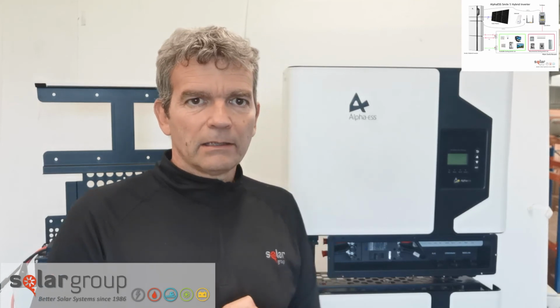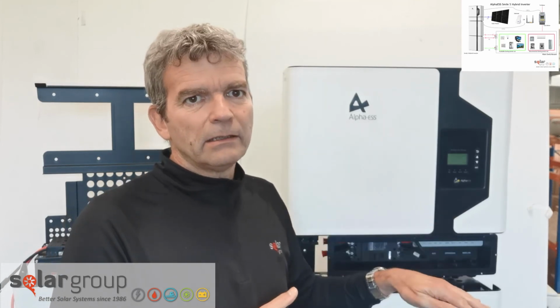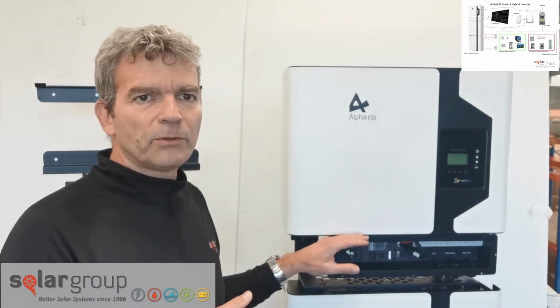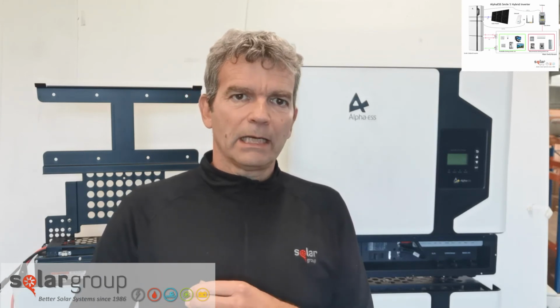Finally, shut down the main and make sure everything you put on the backup is actually working, so it should keep working: UPS, lights, sockets, water pump, router, everything else, exactly as you planned. If that test is passed, then this system will be able to handle power cuts correctly, and it will charge the battery during the power cut as well.